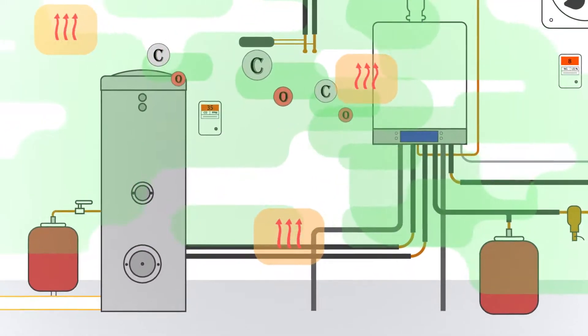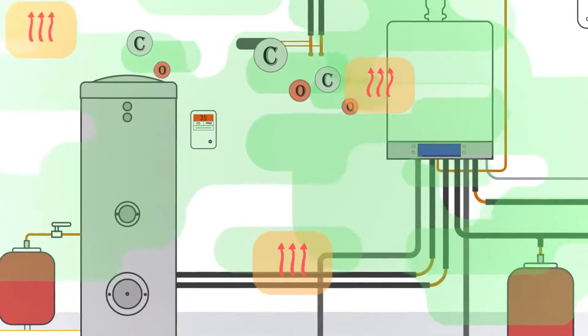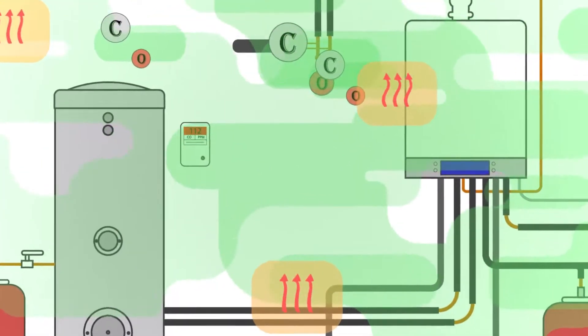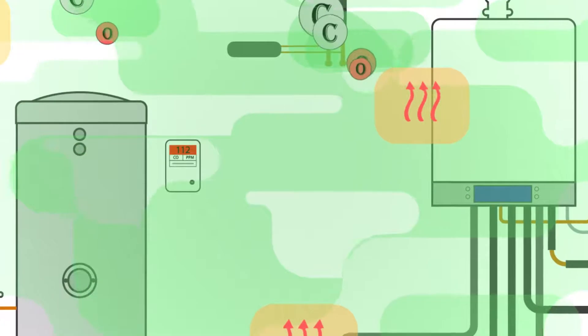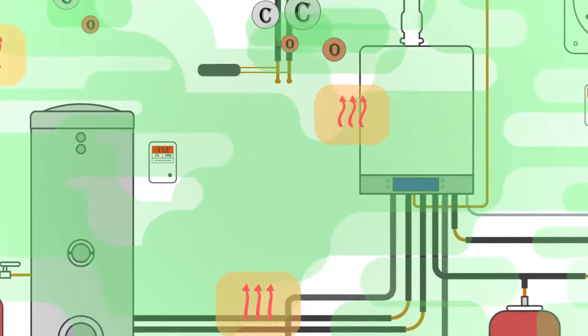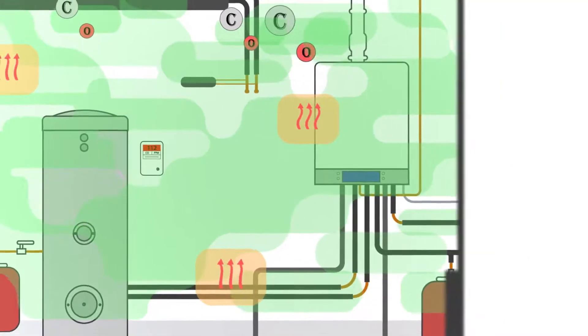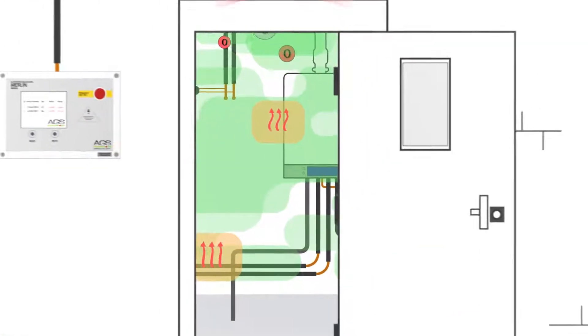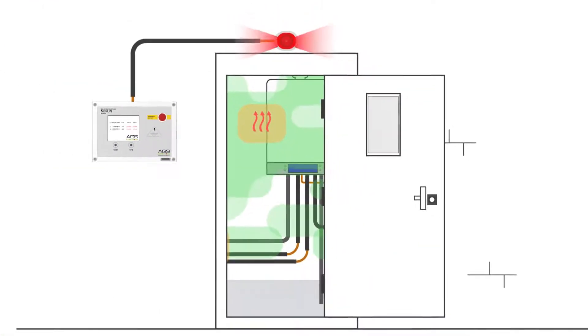Carbon monoxide detectors can be used as a diagnostic tool, identifying problems with the flues, ductwork, or fans. You should not have CO or other harmful gases created by the combustion process in the mechanical room. If you do, you have a life safety issue and a problem you should be aware of.